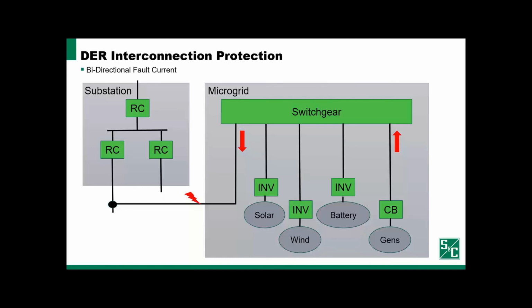Now, clearly, the protective devices that respond are different in each of these situations, but we're seeing fault current in both. So it becomes essential and very valuable to detect the direction of fault current in microgrids and change protective device behavior as a function of the direction that we're measuring fault current flowing in, to ensure we have a selective, coordinated protective response where the right protective devices are operating to minimize the extent of outage.